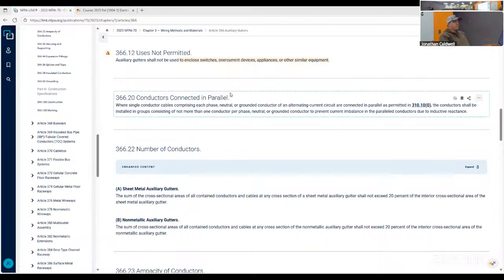And this one's a hard one, because if you are just doing distribution out of a gutter, you're going to have to break it apart at some point, right? So just try to keep them as grouped as possible until you do the distribution, and then you can fan out from there. And that just comes into if you're tapping for motors or something like that. Also some utilities, well, even Iowa Power still has some old services like that. And some commercial buildings where they'll tap out of inside of a gutter and hit multiple meters. And services like that, so.